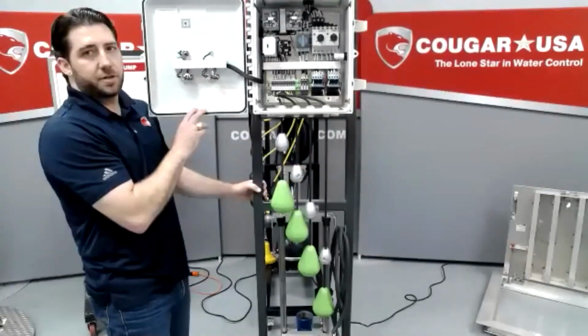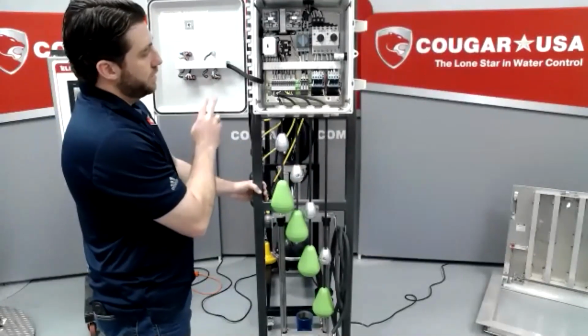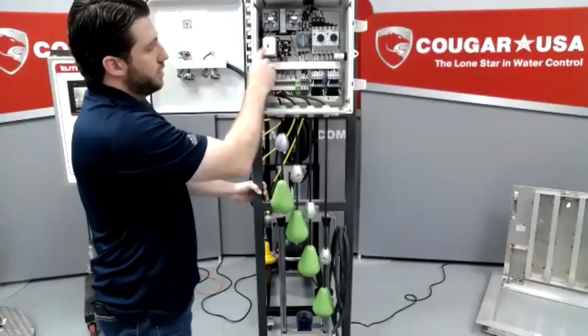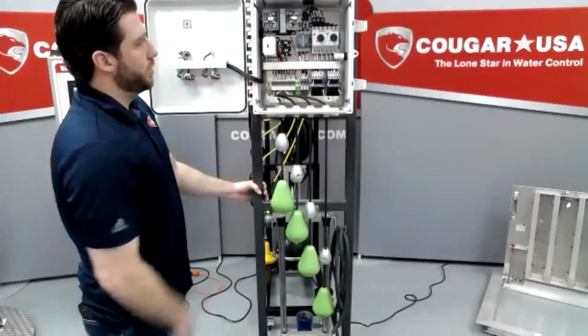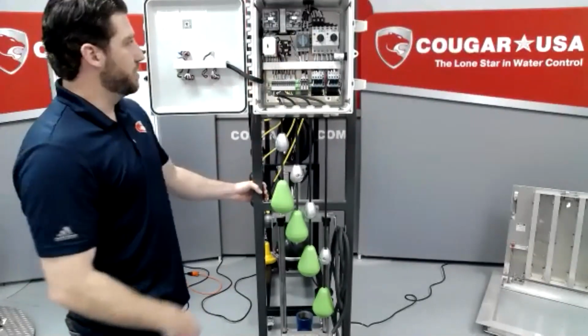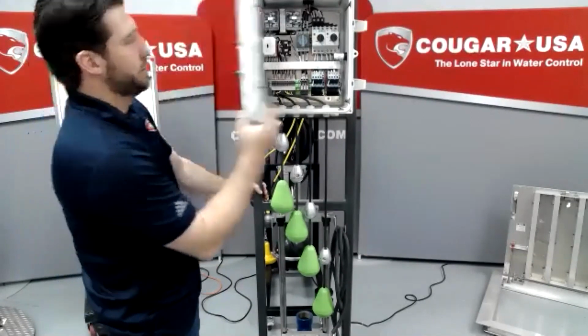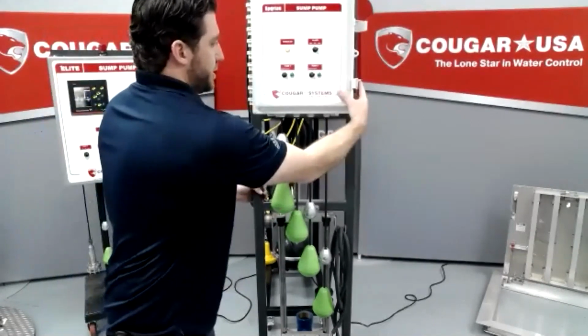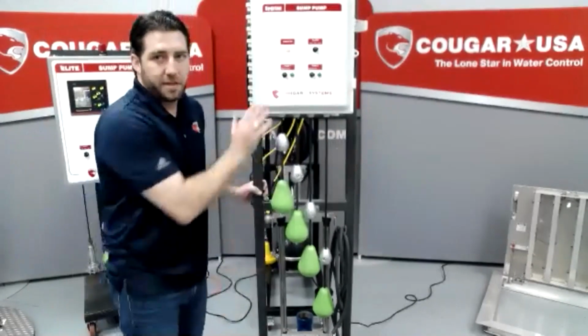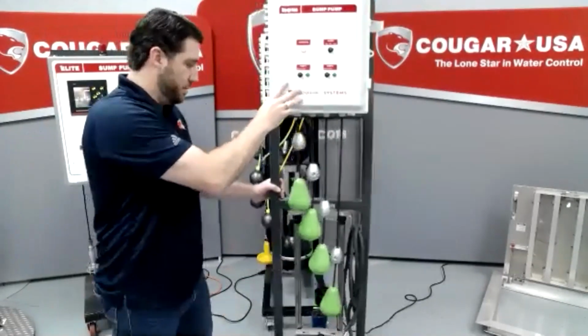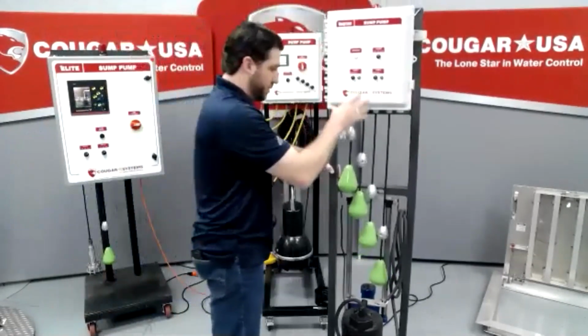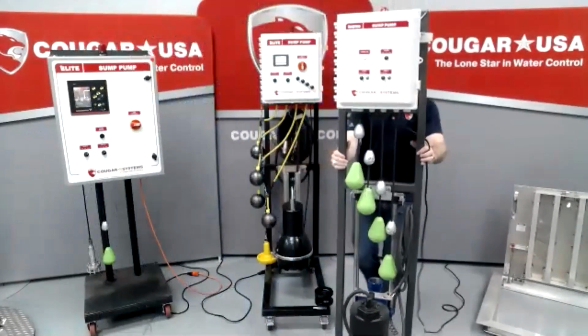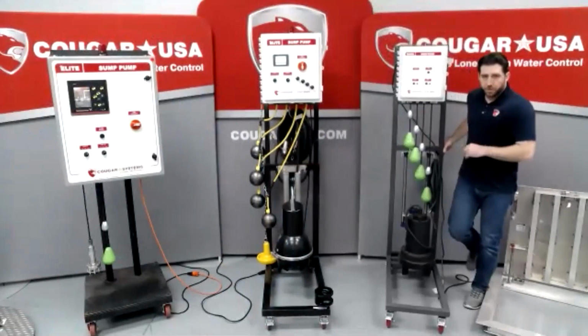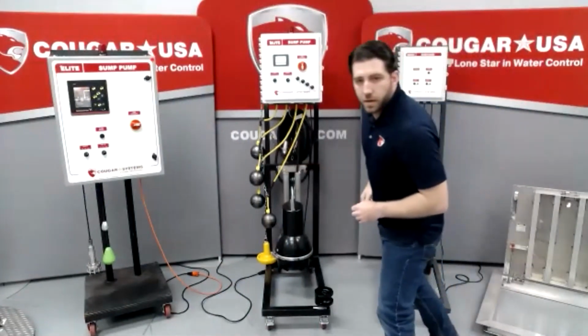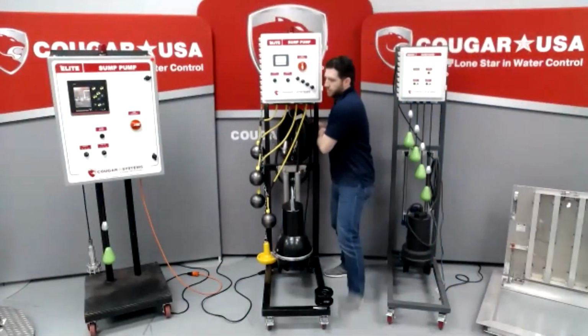And then just to show you the insides of these, again, we just have the relays here, alternating relay, and then our motor controls on the right over there. So it's a pretty basic control panel that can be used for single pump applications. A lot of times we use this style when we're doing elevator pits that require 3-phase motor controls, just because it's a simple application. But really what we're going to want to use more than that is going to be this one.